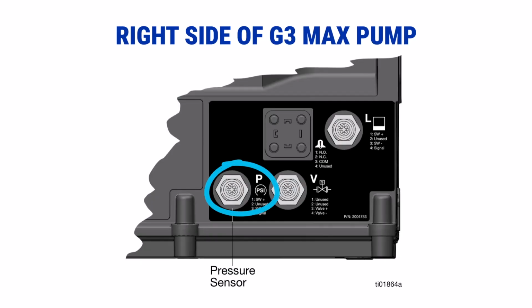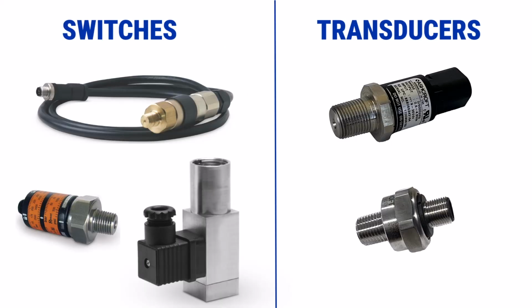Pressure is the input labeled P on the side of the G3 Max, and it is designed to monitor a single-line parallel metering system, otherwise known as an injector system. The P pressure input is connected to a pressure sensor, either a switch or a transducer, which allows the pump to know when to stop pumping.